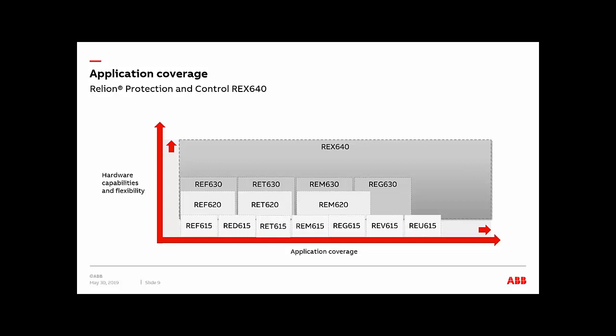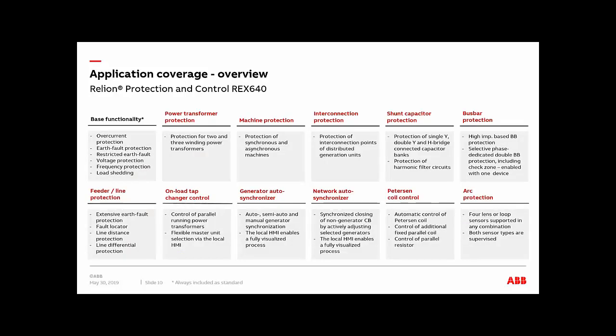So you do have a product that pretty much gives you a comprehensive protection and control package, going all the way to the 630 family of relays. When it comes to the packages, you always get a base functionality with the relay that will give you overcurrent protection. You're going to have ground fault protection, restricted earth fault. You're going to have your voltage elements available to you as well, frequency and load shedding protection.